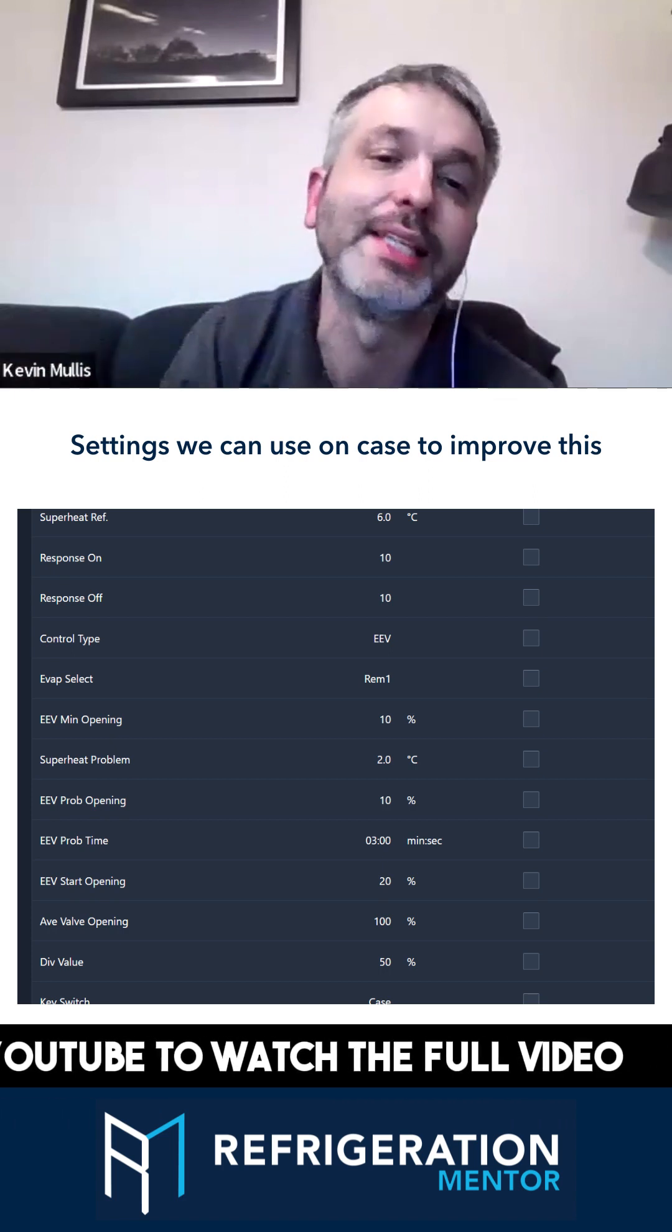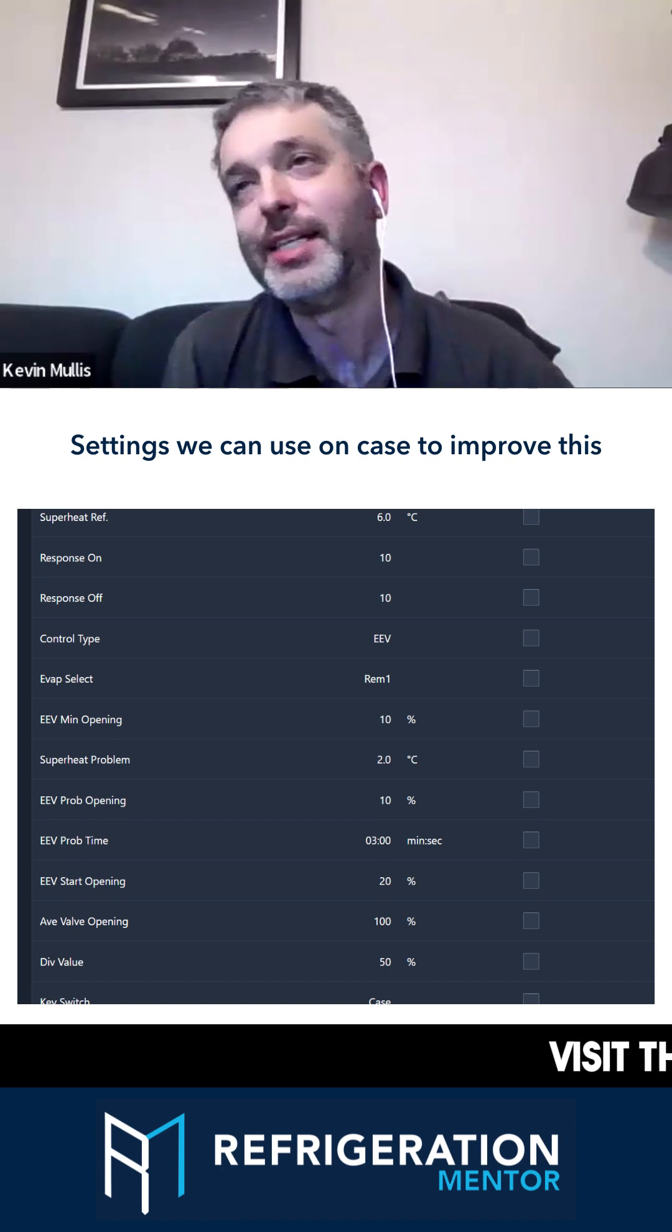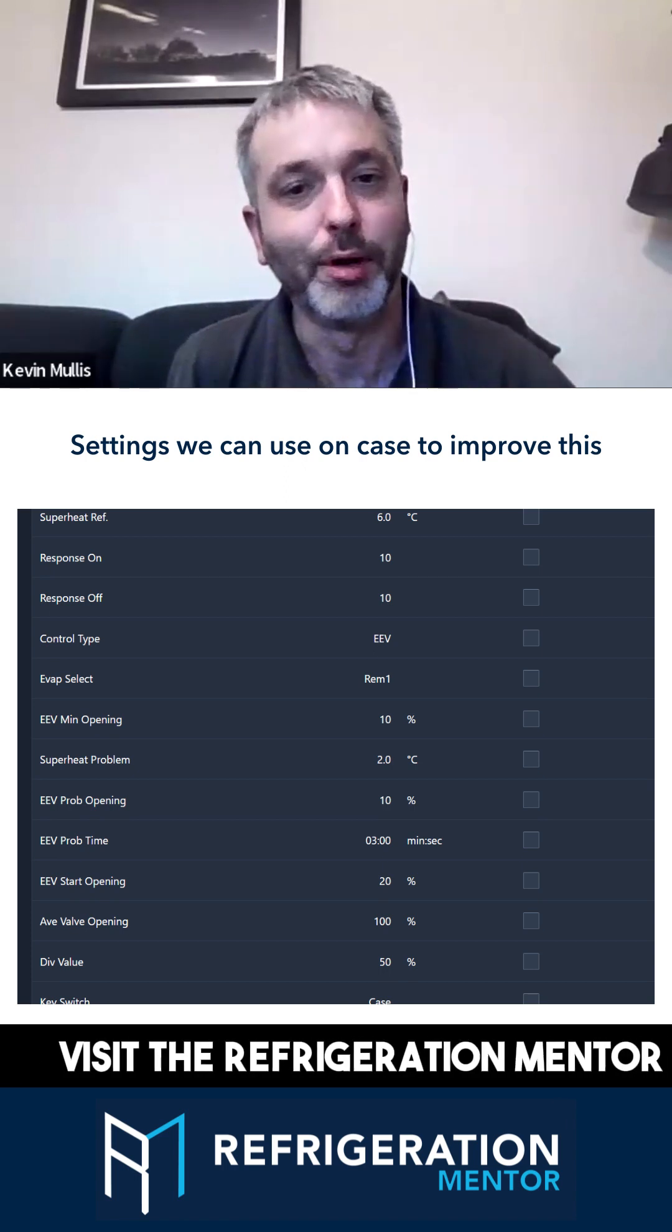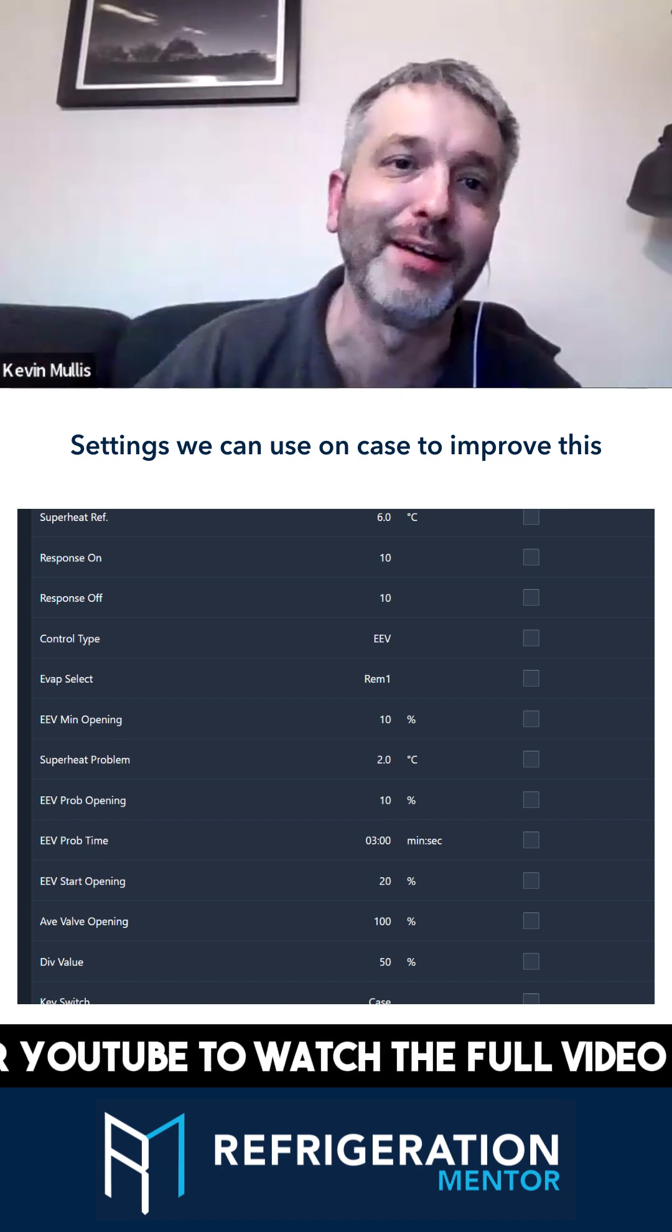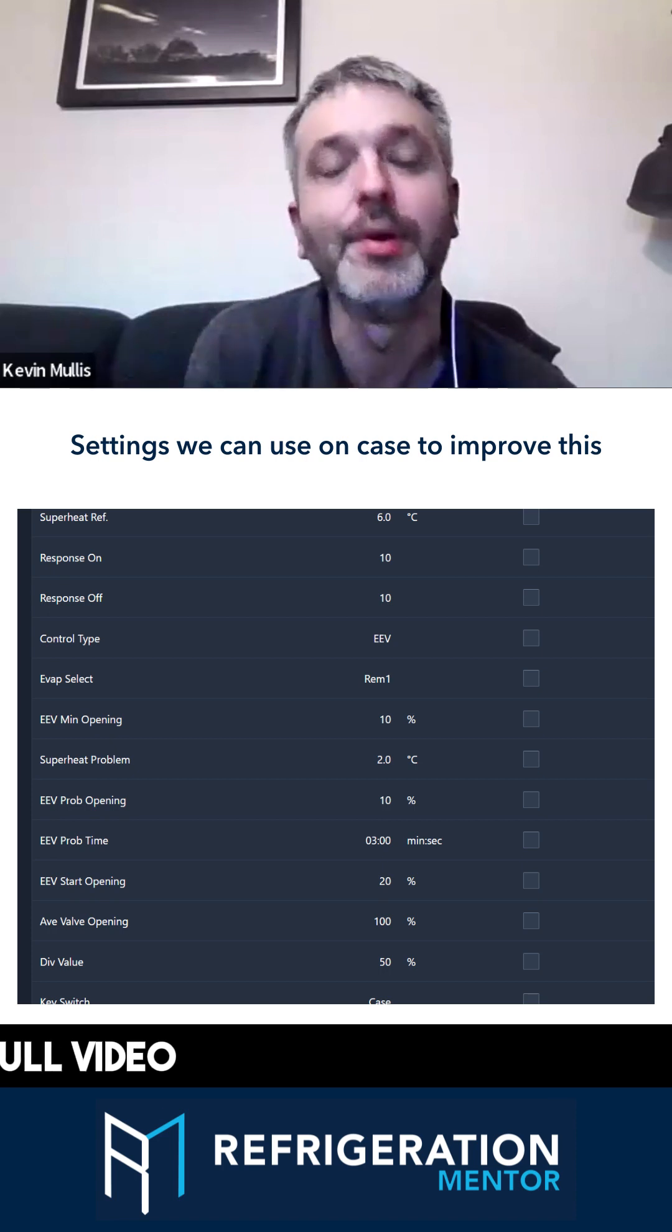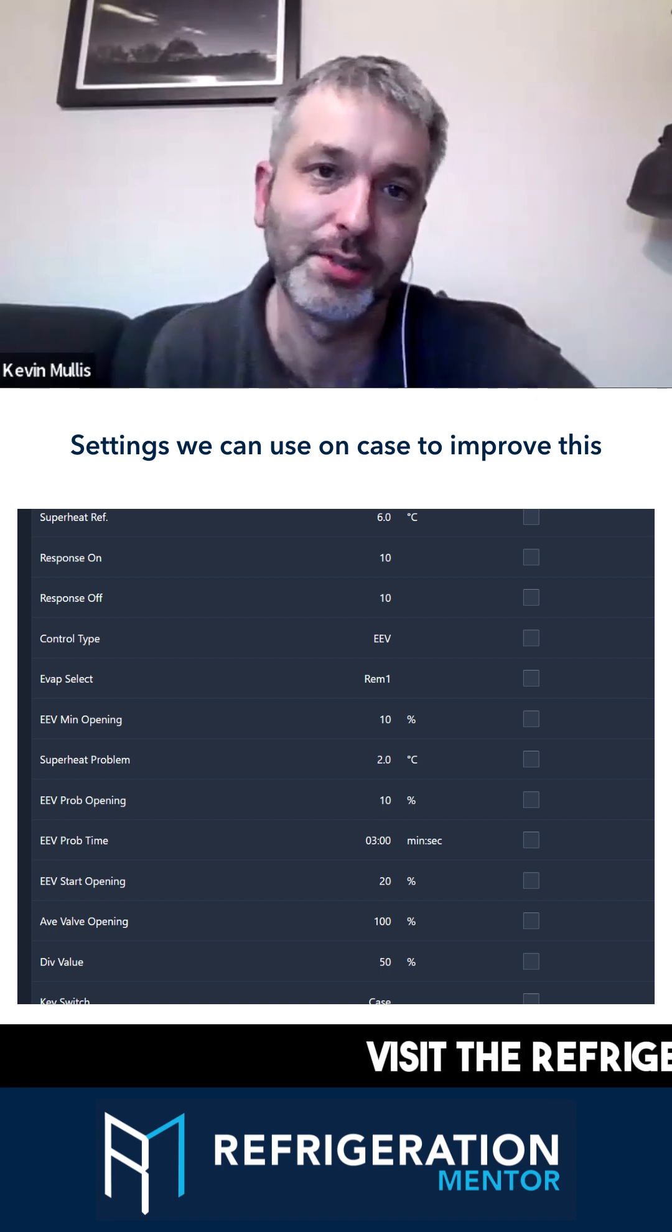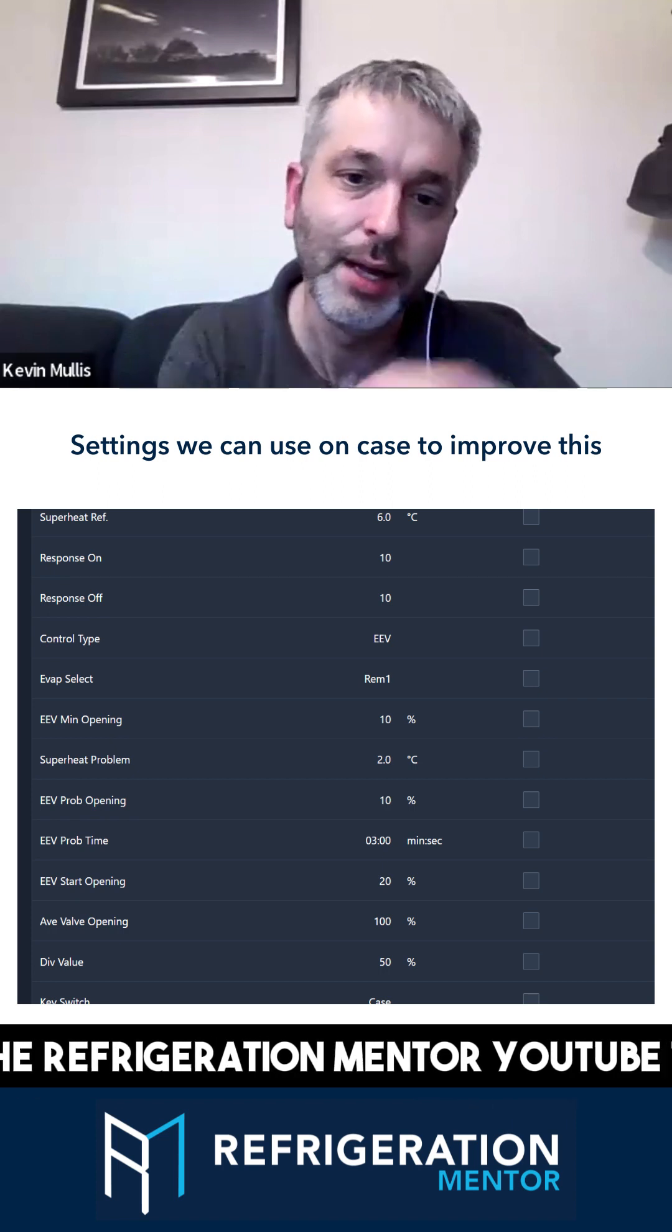All these things are telling you there's a problem with the coil. It's just a question of how much you need to keep that coil running and doing a little bit if there's a minor problem, or whether you just go, no, rack protection is the key here, so I'm going to shut that valve the moment the superheat looks terrible. You know your systems better than I do as to what's priority in that regard and what your system can cope with.